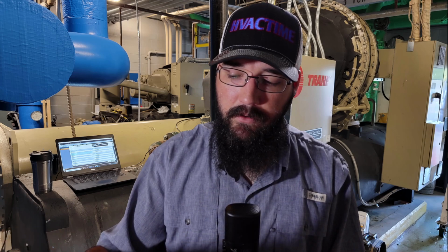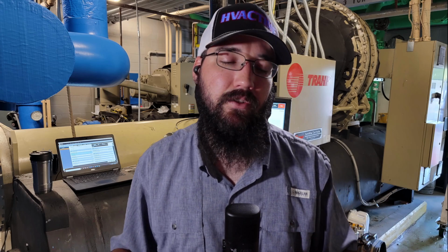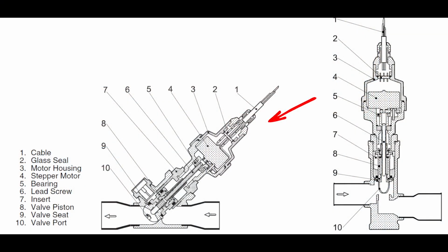Now, the valves you're going to find in a chiller are not going to be the same styles that you're going to see in VRF or mini split or even regular split systems in today's standards. Not saying there won't ever be any crossover, but for the most part, we're talking about valves at a very different scale. For these smaller valves, the more popular version has a removable head. With our modern valves, we don't have that. So here's an example of a very typical modern valve we would see, or the two different styles.